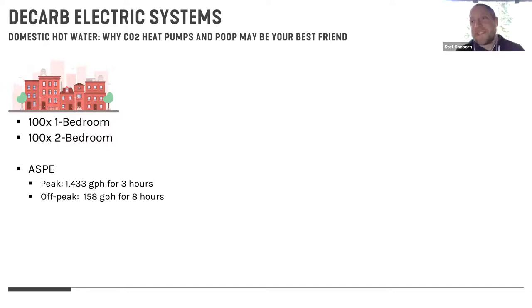So I went ahead and ran a couple of scenarios just to give you an idea of how your choice of heat pump and your choice of source energy can dramatically change the other tangential impacts of your system. As a case study, I'm going to say it's a 200 bedroom multifamily apartment building, six stories, run of the mill, equally split between one and two bedrooms. When I run my ASPE calc for peak water flow, I see about a 1400 gallon per hour peak for 3 hours. That happens twice a day, morning and evening. And then my off peak is somewhere around 158, pretty low gallons per hour.